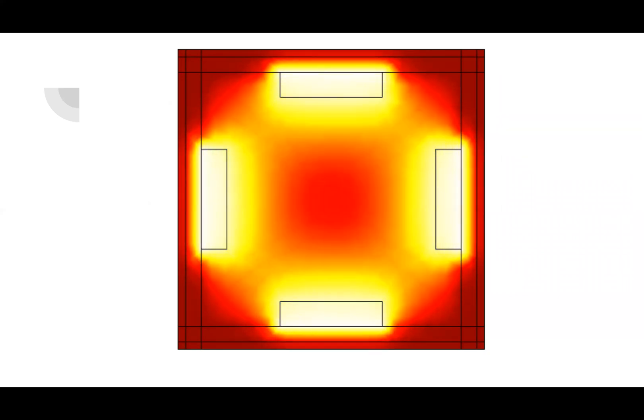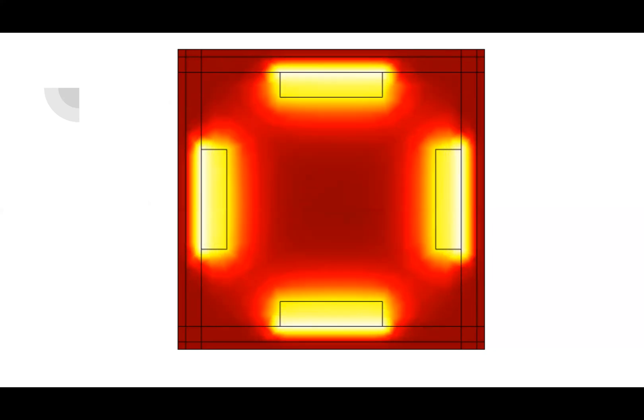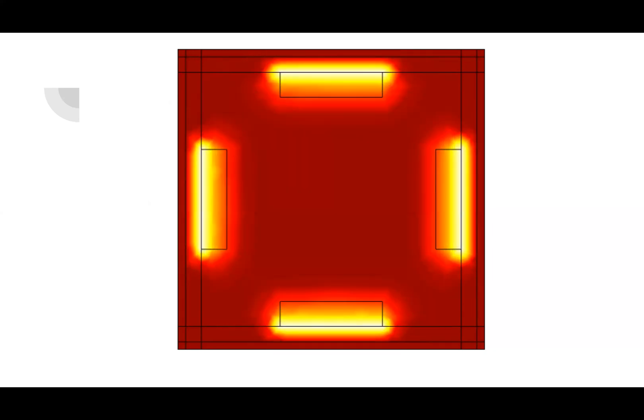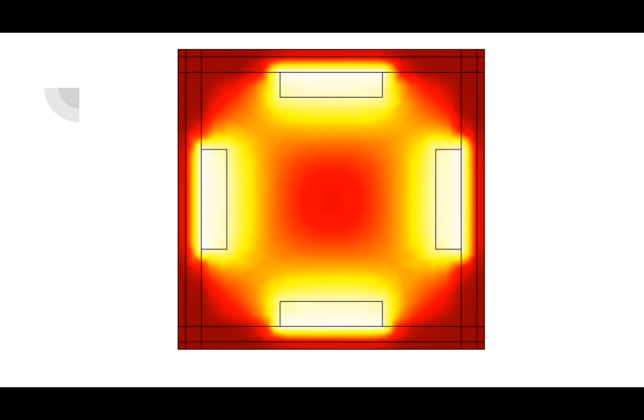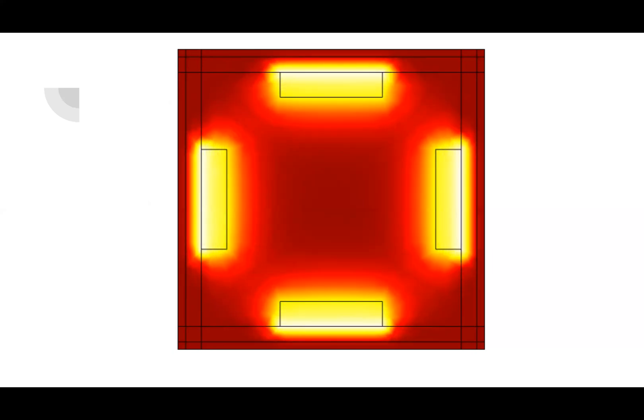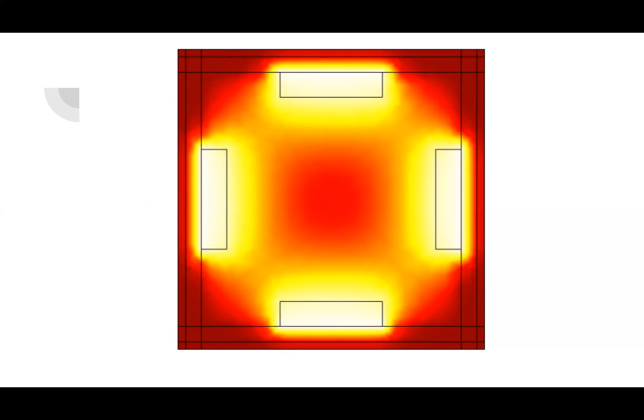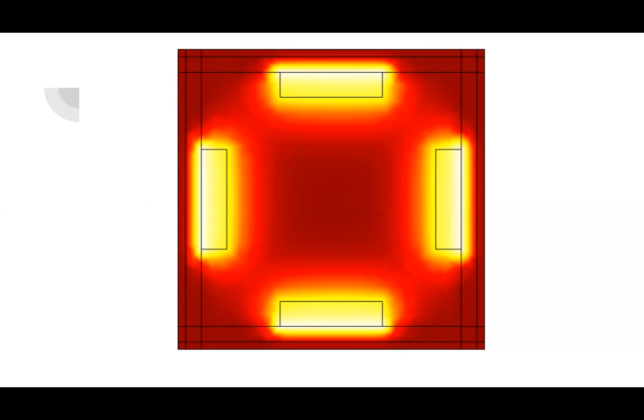So here is our first simulation of the radiators on the wall. First thing we did was determine how many 1.5 kilowatt radiators would be needed to efficiently heat our room. After many simulations, we determined that we would need four of them. We then ran simulations with all three of the different insulations, and we determined that mineral wool was the best because it had the least amount of heat loss, and that is the simulation you see here.